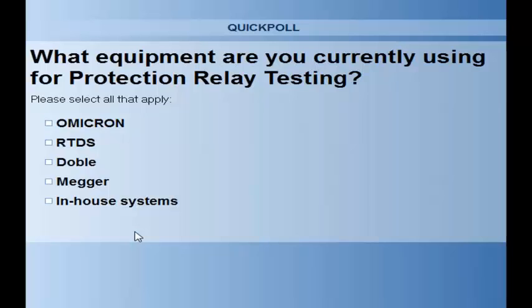To summarize the live demo: we exported data from TestView to Microsoft Excel in order to analyze data acquired through 700 tests. As a result, we found a significant amount of situations for which the relay tripped but should not have, or the relay did not trip although it should have. This is a good example of the test you most likely want to run before integrating your relay into a real power system. You can then directly go to your relay manufacturer and ask what's going on.